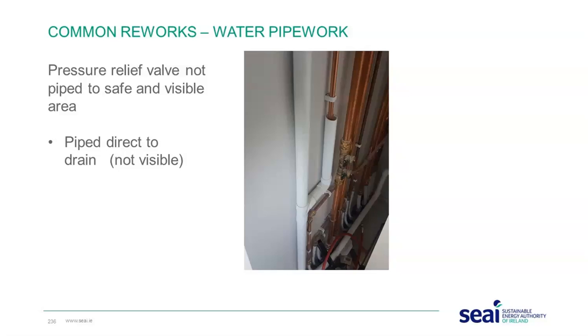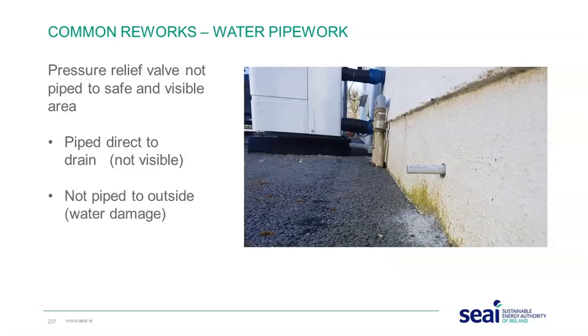What we ask is please fit some means that the homeowner can see that they have an issue, so they can give you a shout and say, look, I think there's a problem, I have a pipe dripping here. In this case, we've asked to fit a tundish on it. In this case, we asked just to put an elbow on it so it points down to the ground. In the case of this safety valve blowing off, we ask just to point it downwards to reduce any risk if hot water blows off and may harm someone.